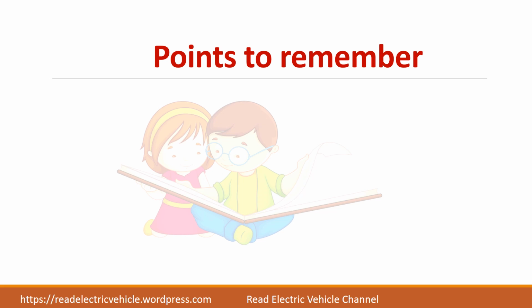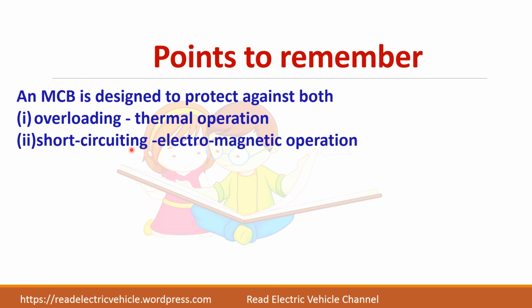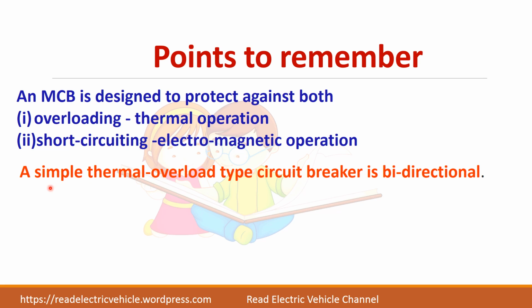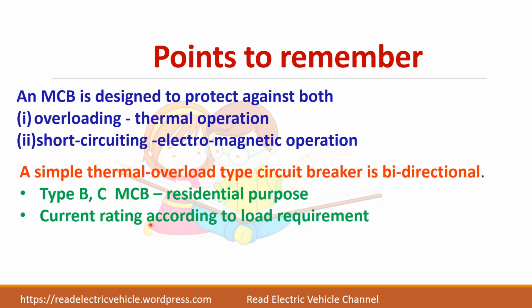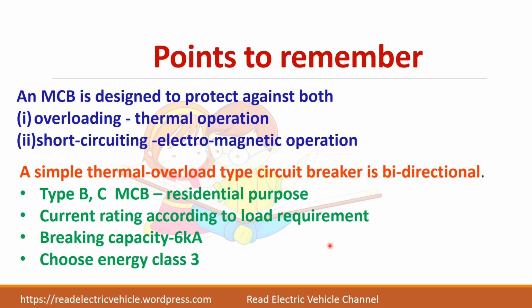An MCB is designed to protect against overloading as well as short circuit. A normal simple thermal overload type circuit breaker is usually bidirectional. It means that you can interchange the line and load terminals. Normally type B and C MCB is used for residential purpose, and the current rating you can choose according to your load. Always choose a breaking capacity of 6 kilo amps for your house, and if the load requirement is high, you can choose 10 kilo amps, and always choose energy class 3.